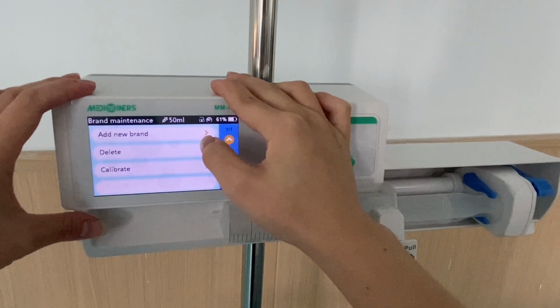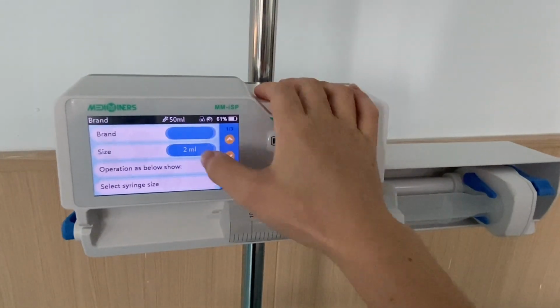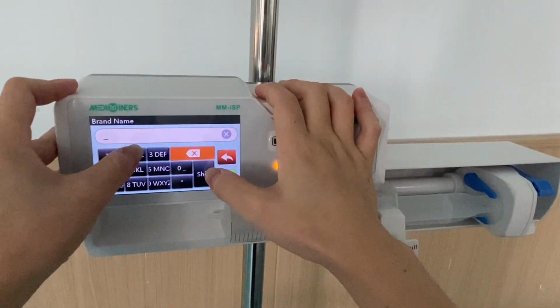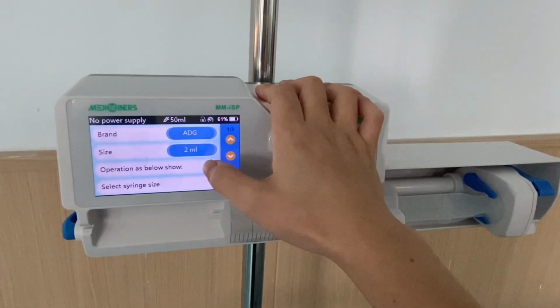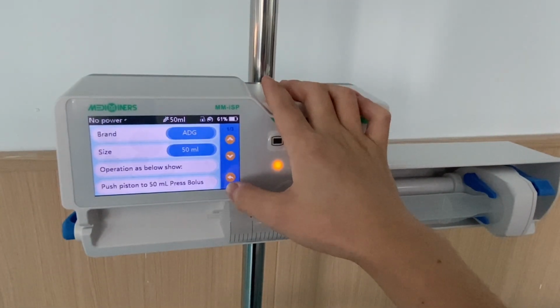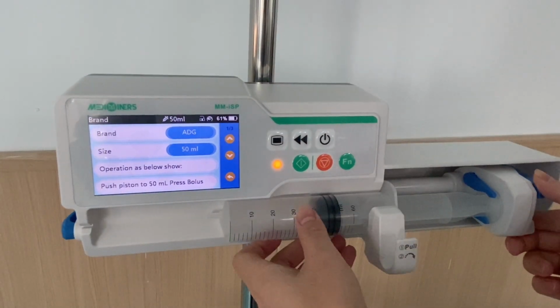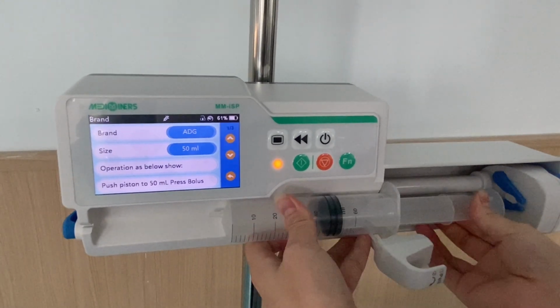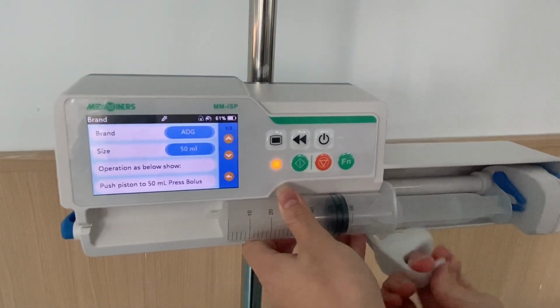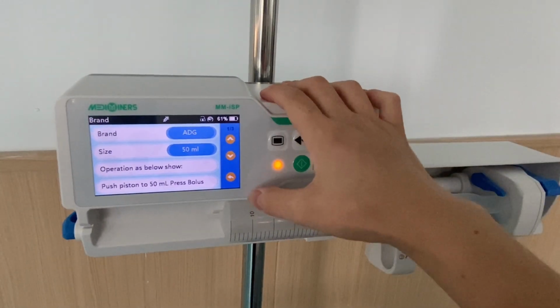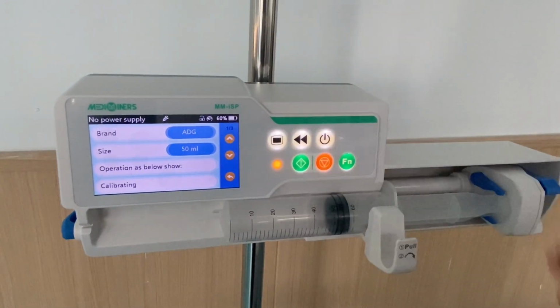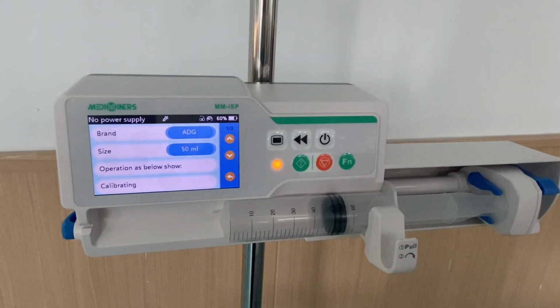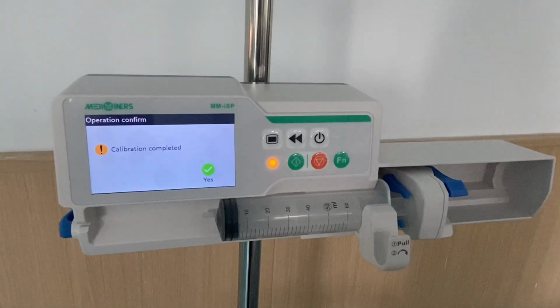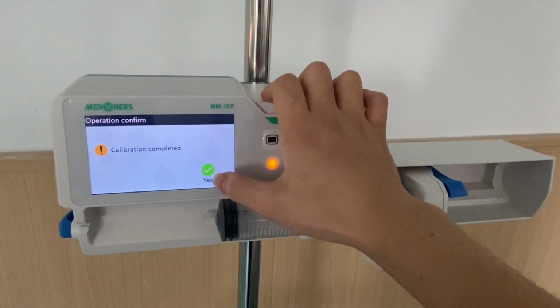If we want to do the maintenance, we should first add a new brand. Let's say ADG. And size, let's choose 50. And we should make sure the size is 50. Now we can start calibrating. This process will take about 3 minutes, so we can wait. Now we can see that the calibration is all completed.